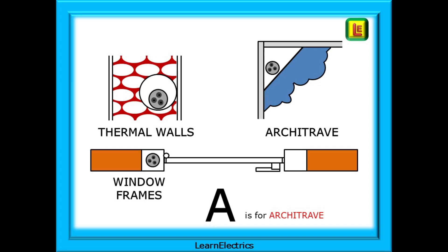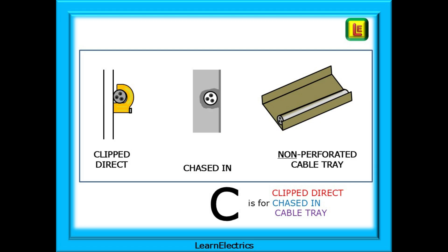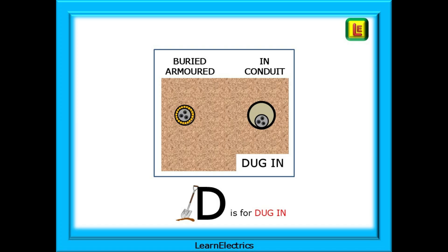We begin with installation method A. Think of A as for architrave, with the cable tucked into the gap behind the architrave. Now think of the cable passing through conduit in a thermal wall - another gap that looks just like the architrave gap. So A is for architrave. Method B is next - trunking is like a box, so B is for box. B is also for cable inside a conduit clipped onto a surface; it just happens to be a round box. So B is for box. C is for clipped direct. C also works for chased-in just below the surface of the plaster, and also for non-perforated cable trays. D is for dug-in - armoured cable or cable in conduit that is buried in the ground must have had a hole dug for it at some time.